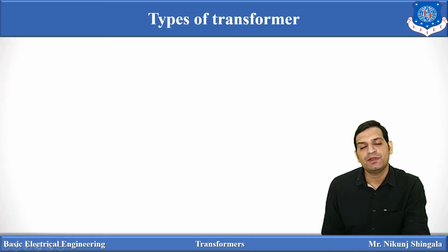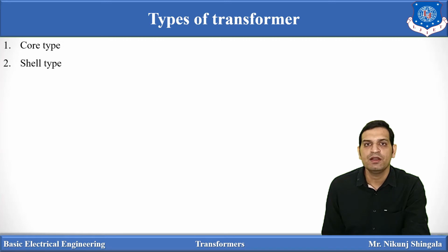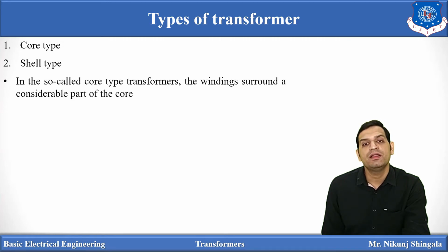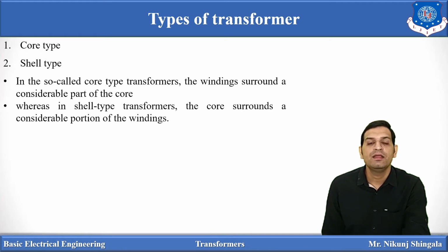Now, types of transformer. Based on how the winding is done in the transformer, it can be classified into two types: core type transformer and shell type transformer. In the core type transformer, the winding surrounds a considerable part of the core. So the winding is around the core. In the shell type transformer, the core surrounds a considerable portion of the winding. So in this case, the core surrounds the winding. In the core type, the winding surrounds the core. This is the basic difference between core type and shell type.